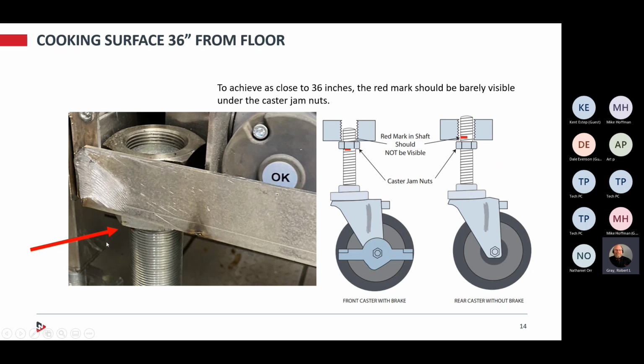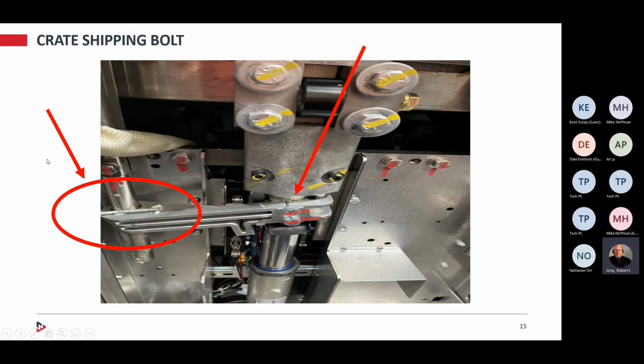And here's another way of looking at it. So that's going to end up about 35 to 35 and a half inches off the floor. Make sure on the test you mark 36 inches. Also during install, when you're uncrating it, there's 2x4s that go on the side of the unit that help to hold the unit in place during shipping. Those bolts that are used to hold that 2x4 in place, do not reuse them.